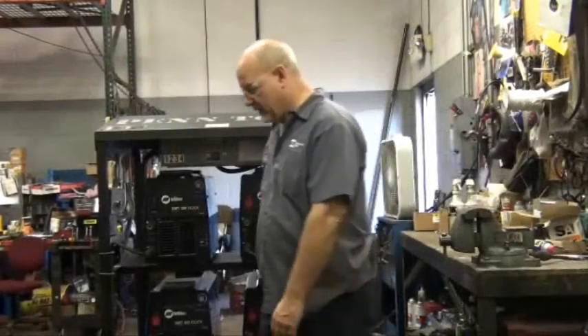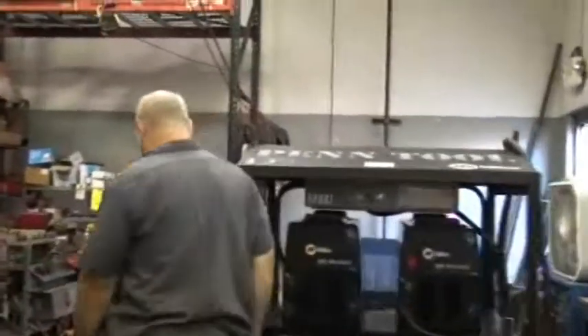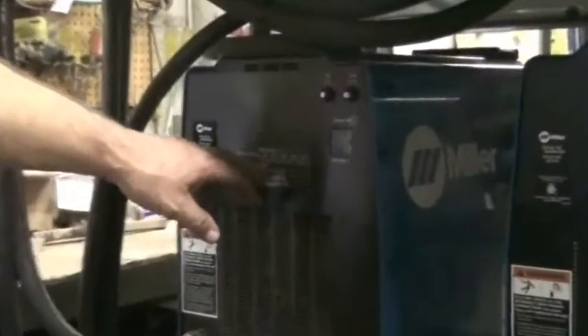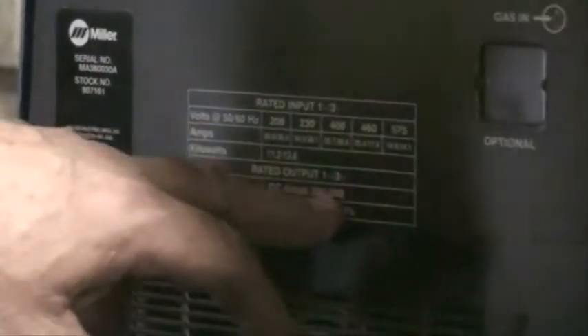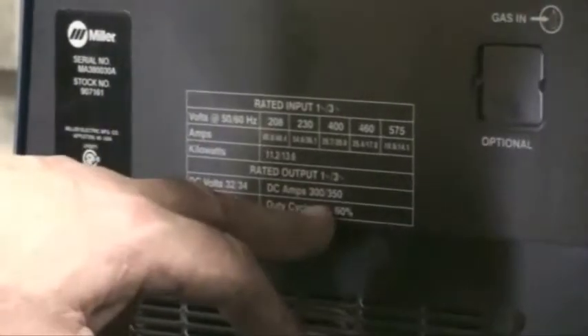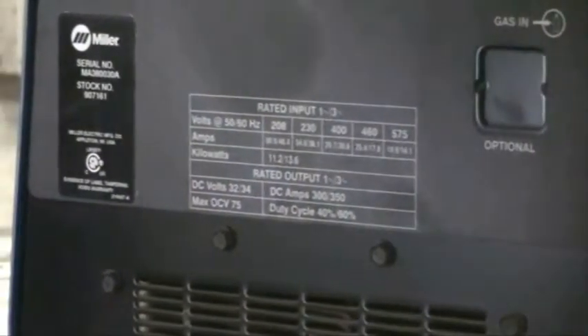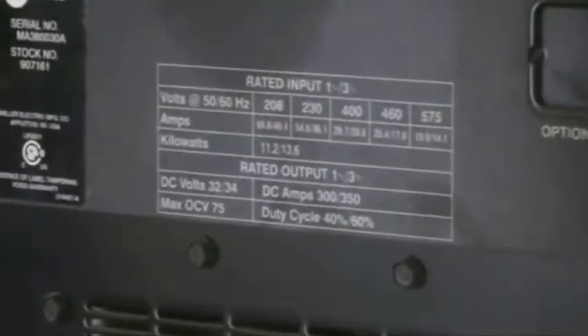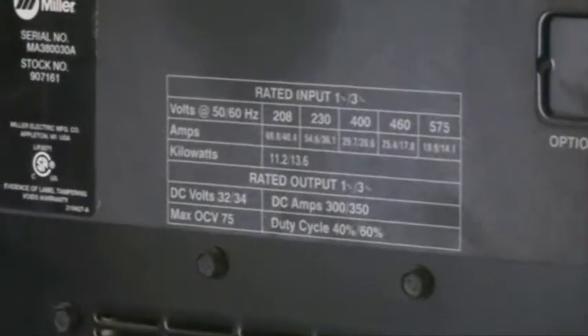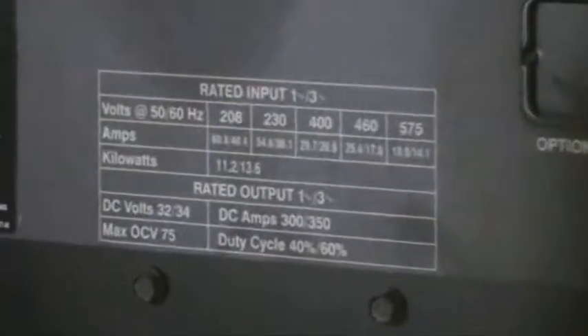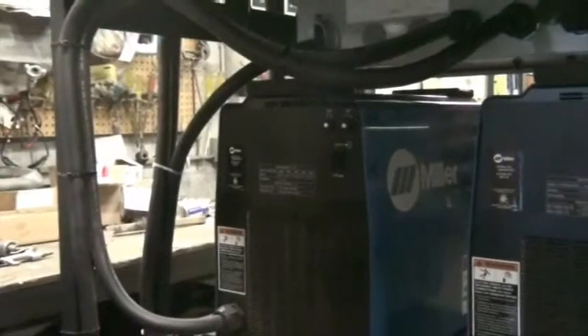First of all, I'd like to take you around the back here and show you the nameplate on these machines for the input. Always look at the back of this to see what your voltages are. This is a 208, 230, 400, 460, 575 machine. Single phase, 3-phase machine. Mostly you use it on the 3-phase, but if you have no access to 3-phase and you need single phase power, you drop off the red line going to the connection box, and you're able to link everything up properly for the single phase use.